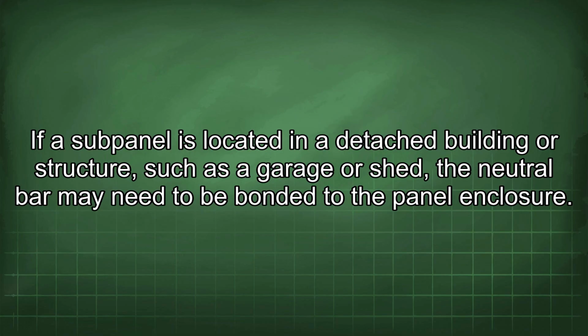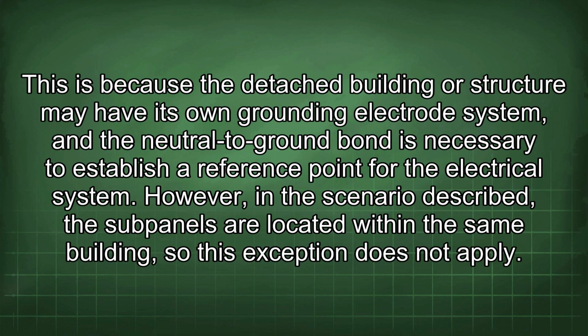If a subpanel is located in a detached building or structure, such as a garage or shed, the neutral bar may need to be bonded to the panel enclosure. This is because the detached building or structure may have its own grounding electrode system, and the neutral to ground bond is necessary to establish a reference point for the electrical system. However, in the scenario described, the subpanels are located within the same building, so this exception does not apply.